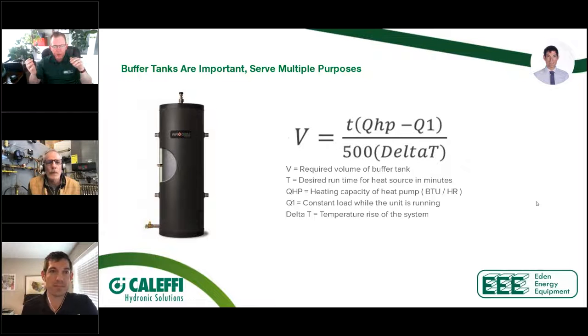In a heat pump situation, we want to also accommodate for micro loads, but Max touched on this. We also want to make sure the heat pump has a minimum runtime of 15 minutes. Now, where does that number come from? It's not from a manufacturer because, again, plug your ears, guys. I know you're with Caleffi. We don't care what the manufacturer says. We now want to know what the research says. So in the United States, IGSHPA has done a lot of research. Here in Canada, OGA has done a lot of research. In the EU, there's a whole plethora of heat pump studies. And sort of the magic number is that 15 minutes.